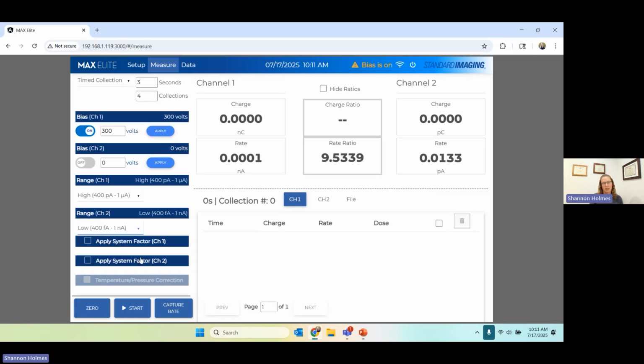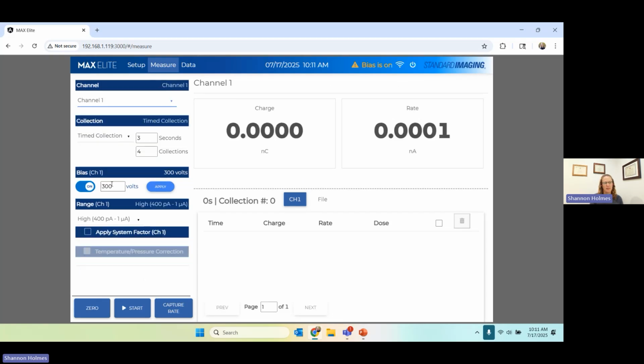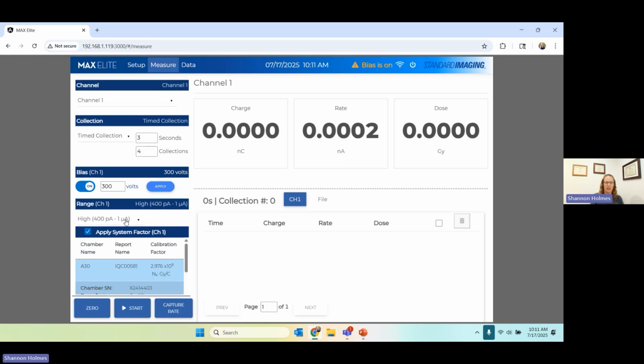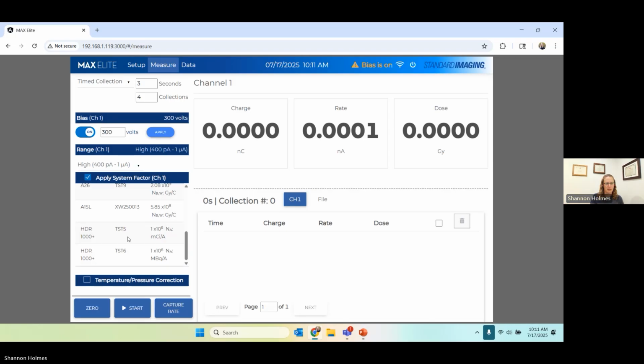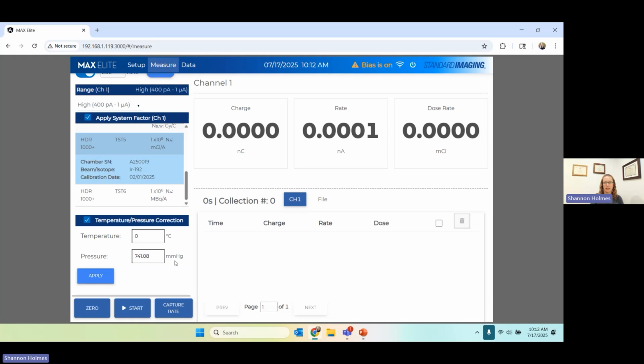And then I can apply system factors for chambers. I'm going to go back to 1 channel just to make this a little cleaner. I can apply system factors if I have a calibrated chamber and/or a well chamber, and I want to see my output in terms of dose or dose rate, whatever matches the entry on my calibration certificate. I can certainly apply those as well. So for instance, if I'm using a well chamber like our HDR 1000 Plus, then my output is in dose rate. And I can apply a temperature-pressure correction to account for the fact that this chamber is vented. We autofill the pressure value using a sensor that's built into the device, so you don't have to enter that value if you don't want to. You can override it.